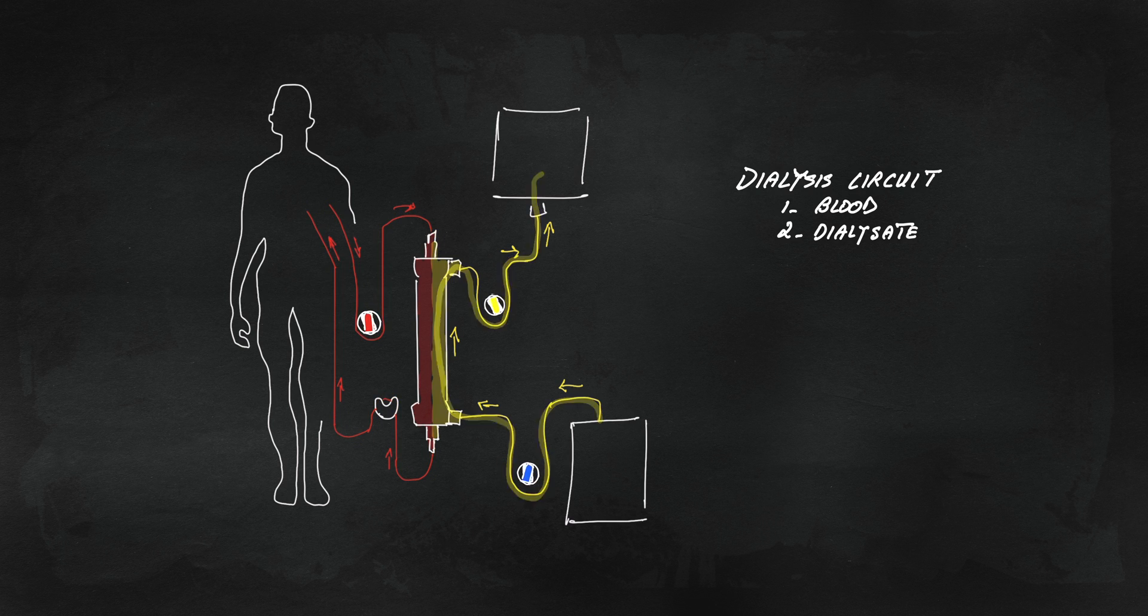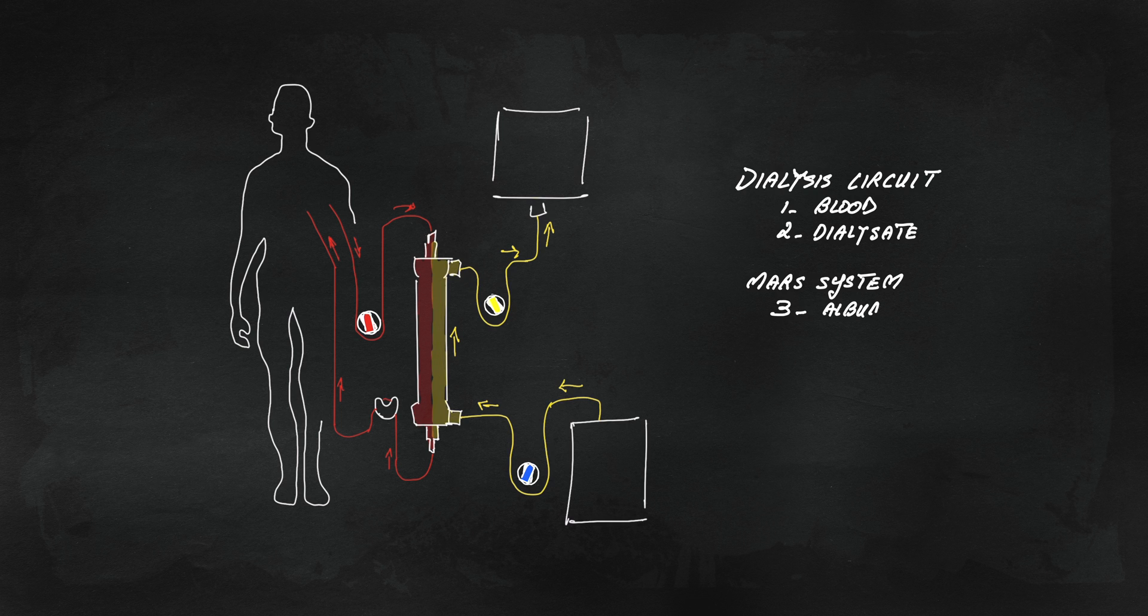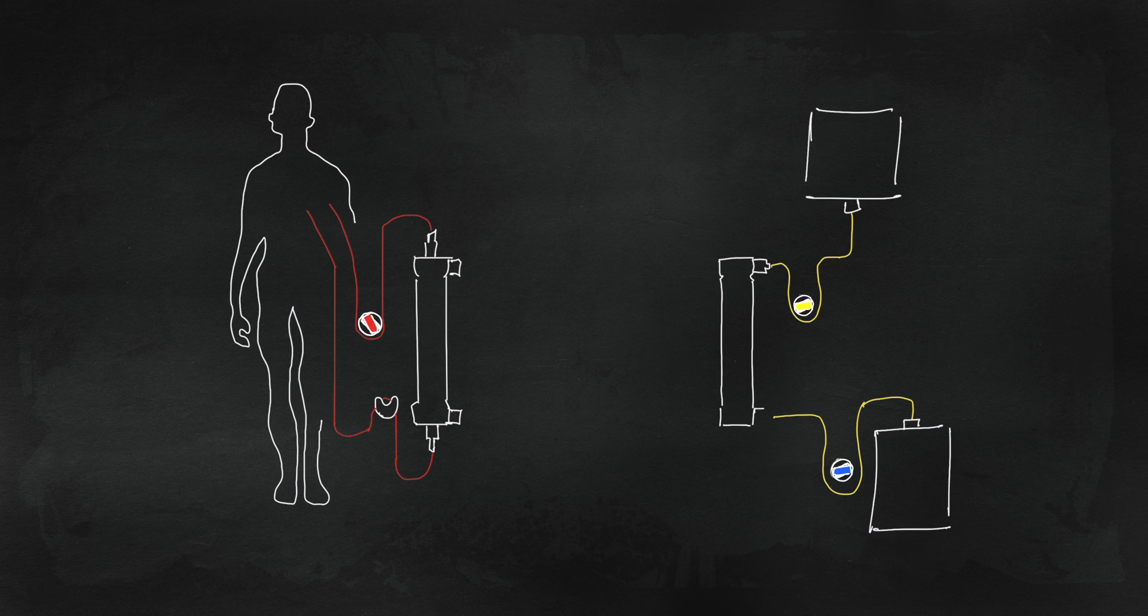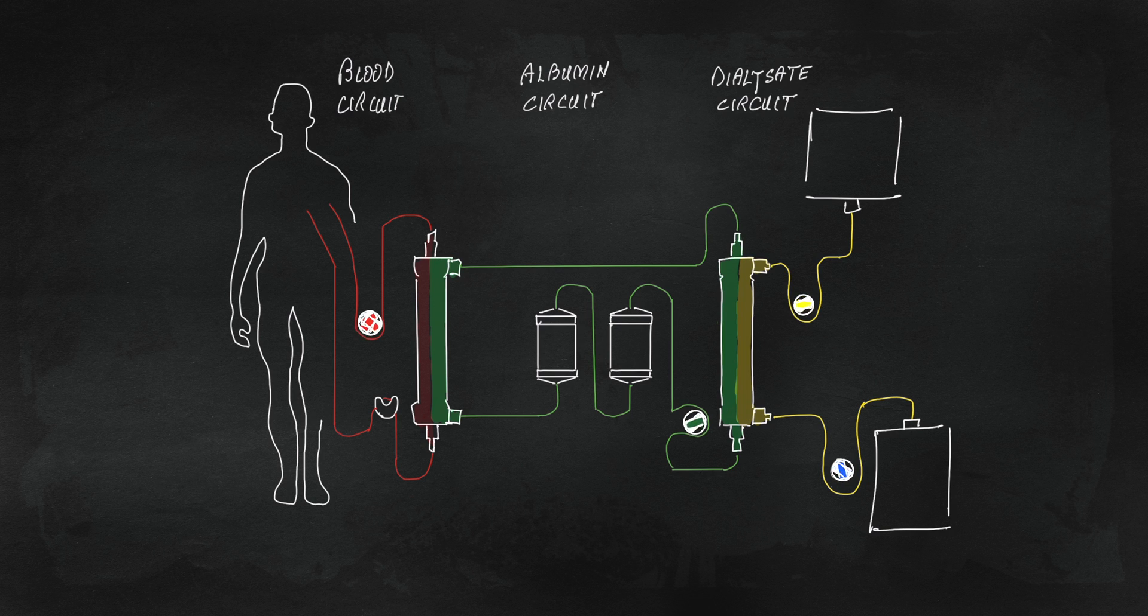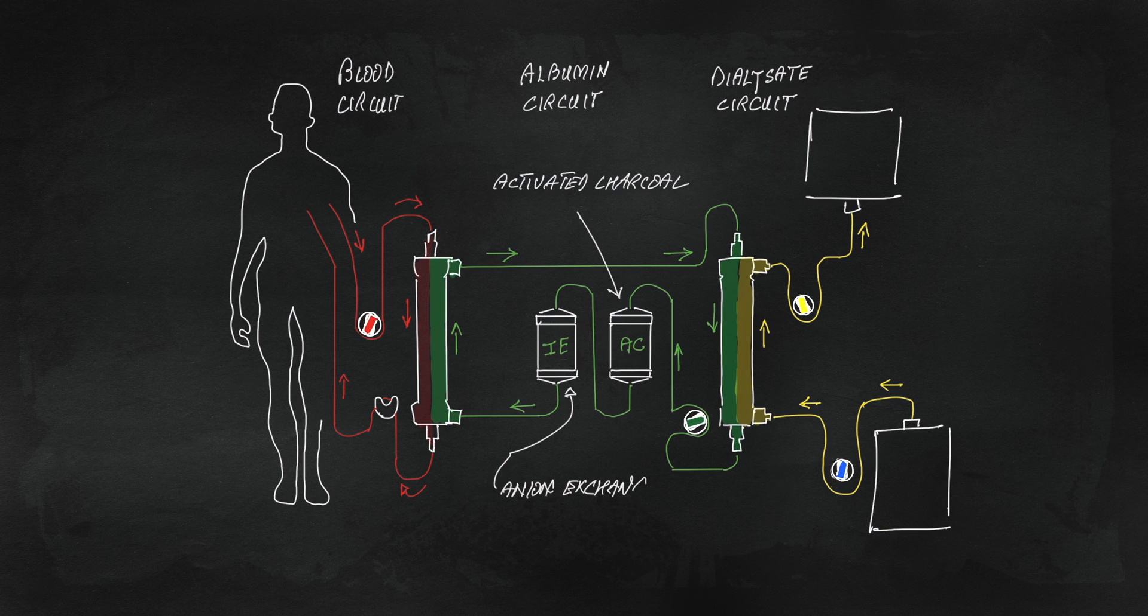With MARS, a third circuit is added, which sits between the blood and dialysate. So in effect, albumin circuit is in contact with patient's blood on one side and regular dialysis on the other side. Within the albumin circuit, we have activated carbon and anion-exchange resin filters. To recap, we have the blood circuit, the albumin circuit which is a closed circuit, and dialysis circuit.